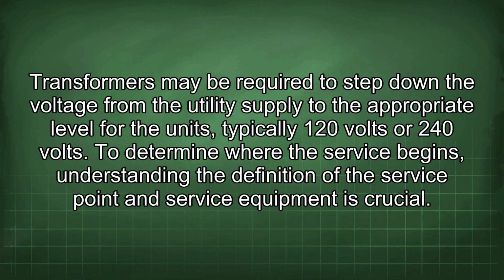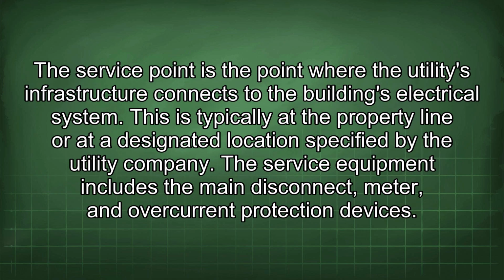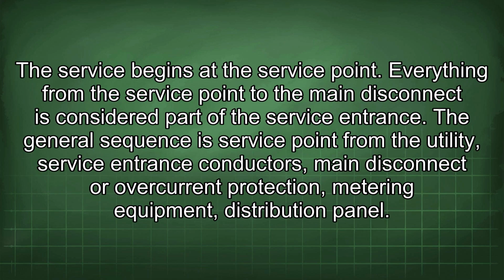To determine where the service begins, understanding the definition of the service point and service equipment is crucial. The service point is the point where the utilities infrastructure connects to the building's electrical system. This is typically the property line or at a designated location specified by the utility company. The service equipment includes the main disconnect, meter, and overcurrent protection devices. The service begins at the service point. Everything from the service point to the main disconnect is considered part of the service entrance.